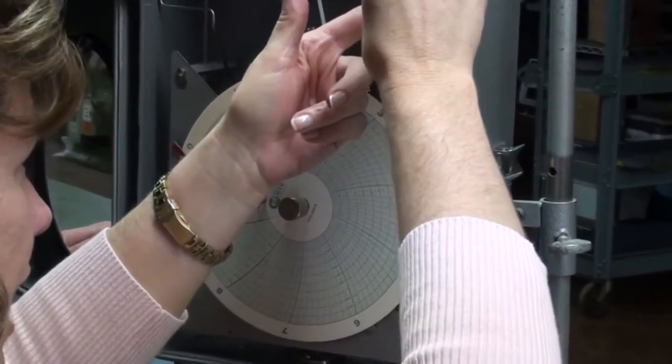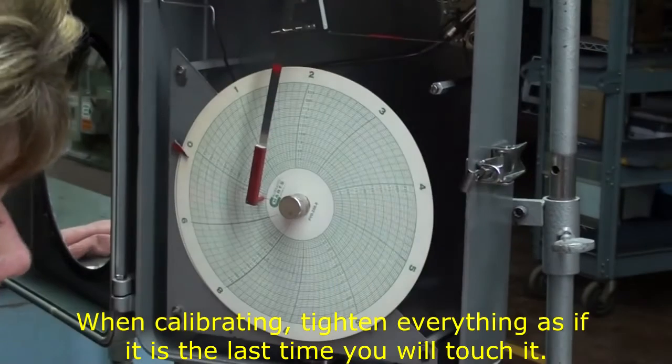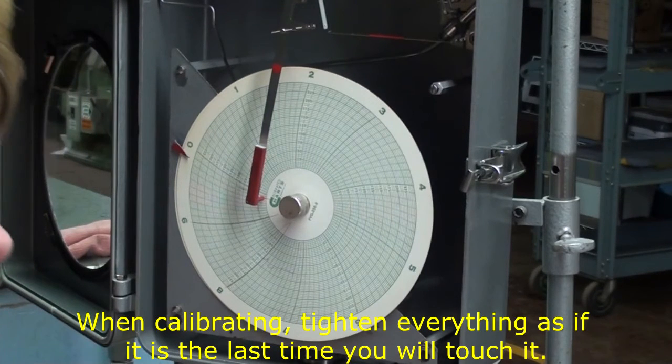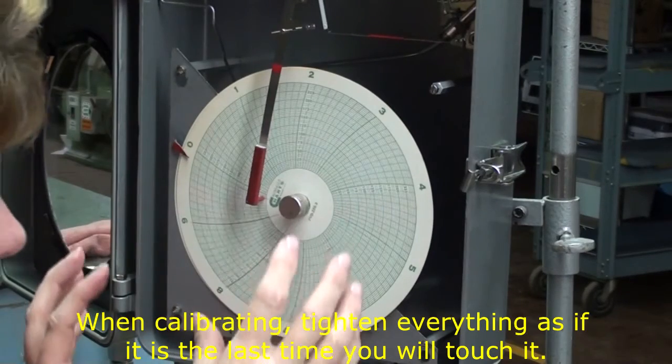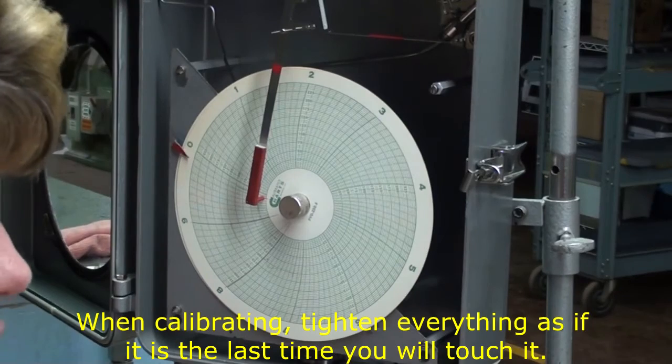And any time you're calibrating a recorder, you really should tighten everything as if it's the last time you will need to. Because if by chance, I get lucky and hit the calibration with the first adjustment, if I go back and tighten anything, then I've messed up my calibration. So anything that you're tightening up on a box, you should tighten it as if it's the last time you're ever going to touch it.